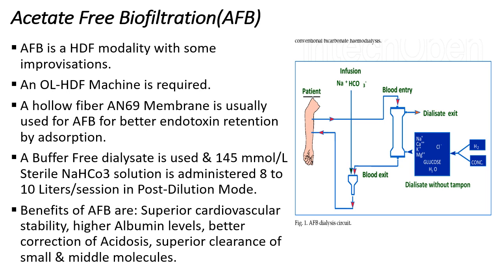The next modality is acetate-free biofiltration, or AFB. It is essentially an improvised online haemodialysis modality in post-dilution mode. An online HDF machine is required along with an AN69 membrane, which is made of a special polymer called polyacrylonitrile with superior endotoxin retention capacity by adsorption. An acetate-free or buffer-free dialysate solution is used. During treatment, a continuous infusion of sodium bicarbonate solution at approximately 145 mmol/L is administered in the venous return line — typically 8 to 10 liters per treatment. Acetate-free biofiltration offers superb cardiovascular stability, increased albumin levels, better correction of metabolic acidosis, and high clearance of small as well as middle molecules.